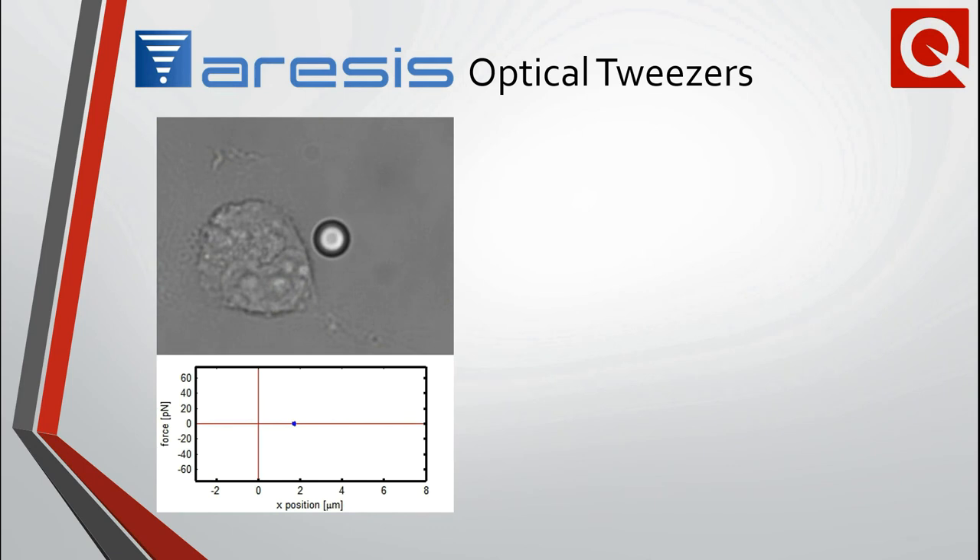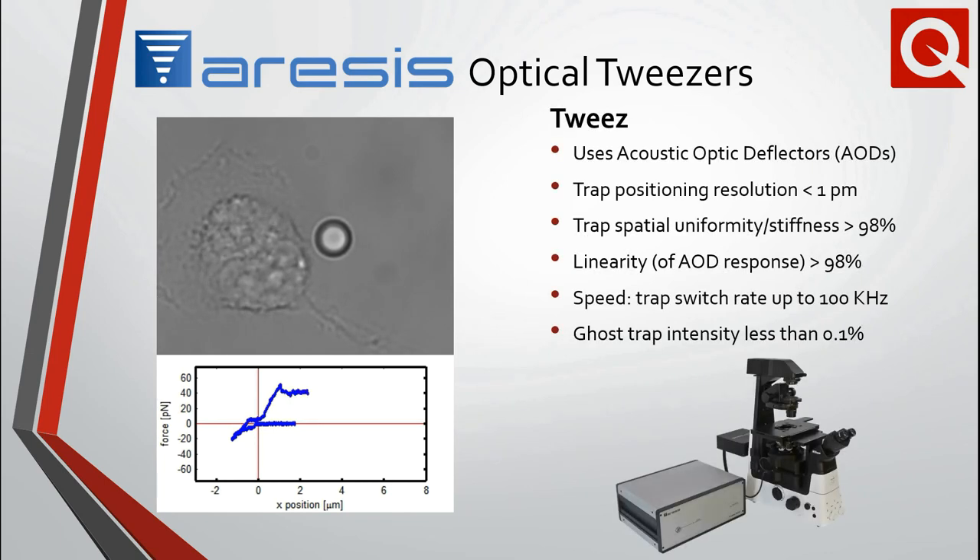Quantum Design also offers solutions for bio- and soft-matter physics. The optical tweezers from Aresis, a company out of Slovenia, are well-established in these research communities. The video demonstrates a live measurement of cell elasticity, where the force-versus-displacement curve shows the strength of cell adhesion to the microbead as it is pushed and retracted from the cell wall — forces on the order of piconewtons. The Tweez instruments use acousto-optic deflectors to obtain high trap-to-trap switch rates while ensuring critically important trap attributes, including field uniformity, trap stability, trap accuracy, and ghost trap elimination.